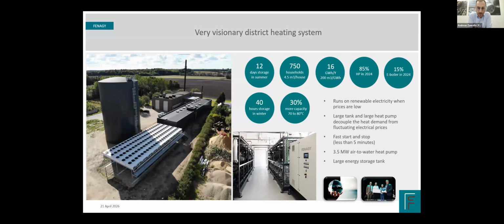One of them is the project I just showed you before, which has a buffer storage of a little more than 3,000 cubic meters, enough for up to 12 days of storage in the summer, maybe 40 hours in the wintertime. This plant not only has our 3.5 megawatt air-to-water heat pumps, but also, if I remember well, a 10 megawatt electric boiler, and they run exclusively on electricity.